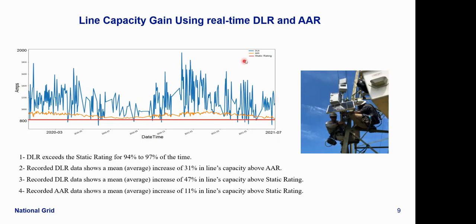The blue line is DLR, and orange is ambient adjusted rating, AAR. AAR is more restrictive in terms of wind speed and so on, so DLR has better visibility over wind speed, icing conditions, sag, and other parameters. The static rating is what most planners use to plan their transmission network. Looking at the data, 94 to 97% of the time, DLR exceeds the static rating.